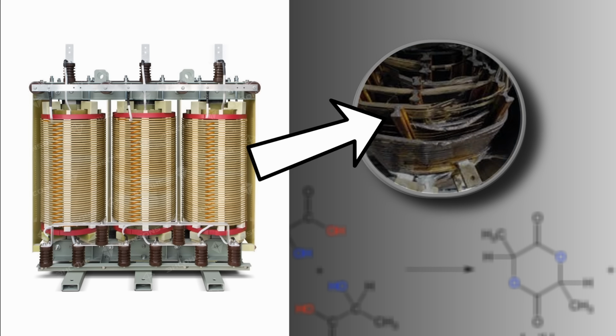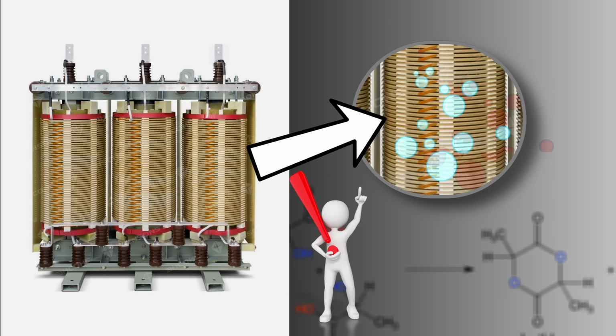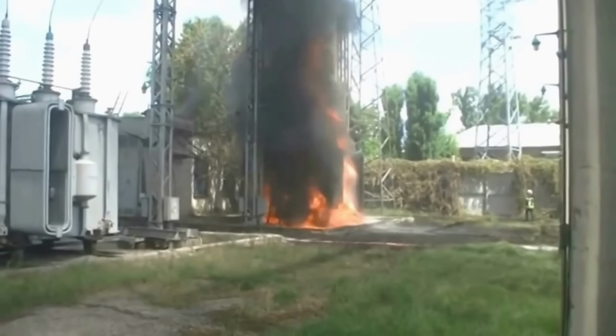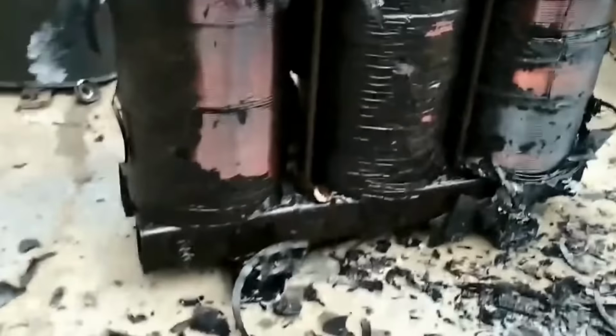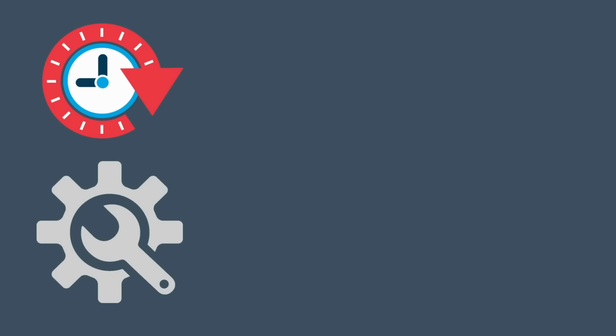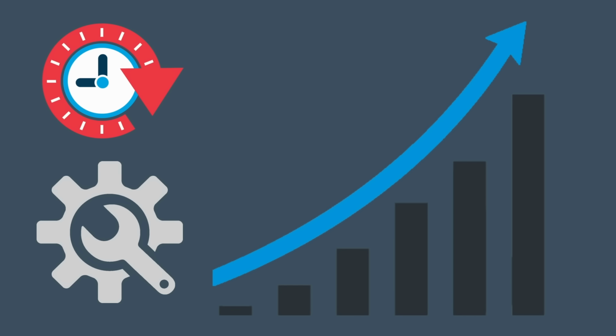Moreover, a high level of water in the paper insulation induces a bubble effect, which sharply decreases the dielectric strength and increases the tank pressure, as well as leads to operation shutdown or failure of a transformer. Therefore, drying of power transformers has a significant effect on the service life of both new and already operating equipment.